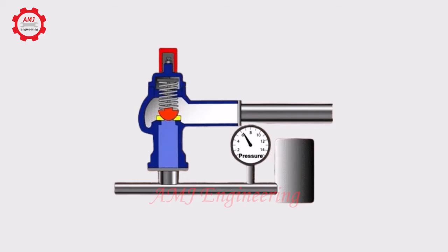When system pressure begins to exceed the setting of the valve spring, the fluid pushes the ball or poppet, allowing a controlled amount of fluid to bypass to the reservoir, maintaining system pressure at the valve setting.